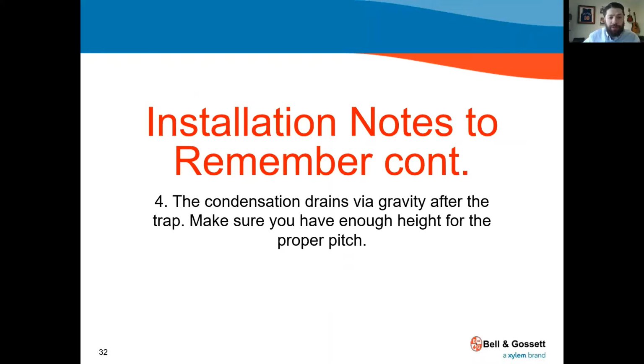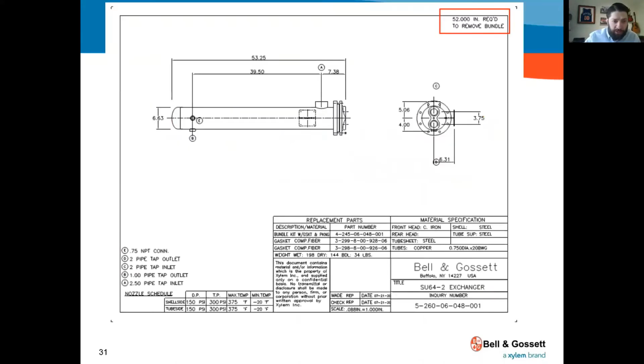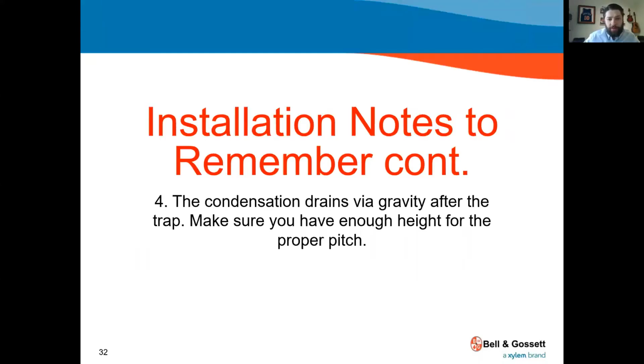More notes to remember, the condensation drains via gravity. So after the trap, make sure you have enough height to pitch properly to your condensate pump. So if you're using the legs, let's say, and it's on the ground, and your condensate pump's a long way away, you got to make sure you've got the proper pitch to get that water to gravity drain into the unit. The pump on that unit is to pump out. So, you know, you're filling that tank just via gravity. So if you look at this, you see what's located B, letter B, that's your outlet there. So you got to make sure after your trap, you got enough gravity.